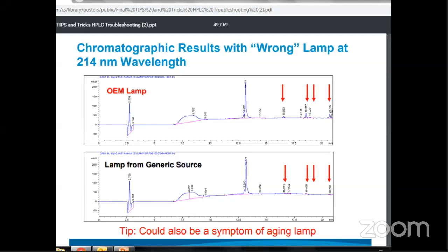The only point I would like to bring up as troubleshooting is that whatever lamp we are using for the detector, it should be of good quality, meaning what is recommended by the vendor. So, OEM. I will bring the exact form back to you maybe at the end of the slides.